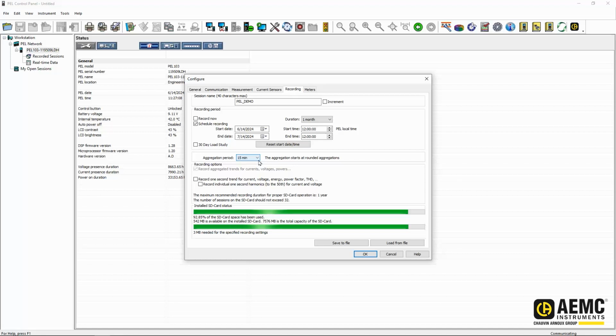If not performing a load study, we can set aggregation periods, which selects how often the instrument averages and stores data over a defined period. For example, a 1-minute aggregation period for voltage on phase 1 would produce a single value representative of the average voltage for a 1-minute period. For the PEL, an aggregation period can start at 1 minute, maximum of 1 hour.